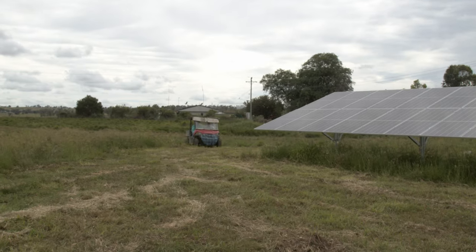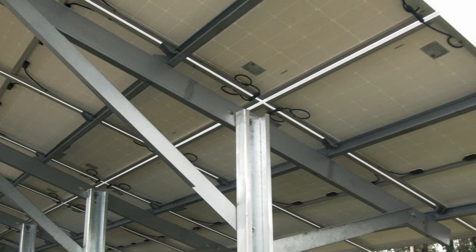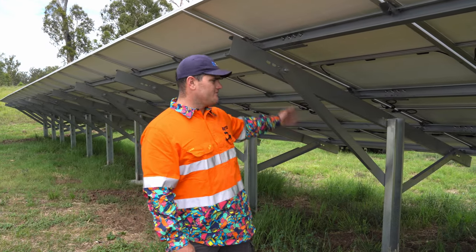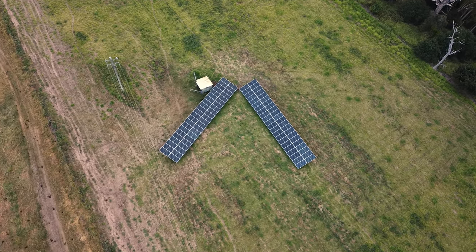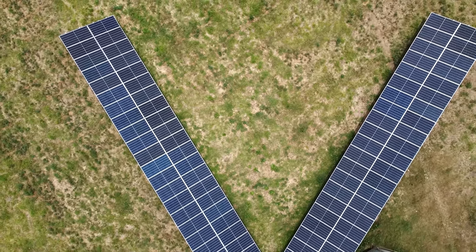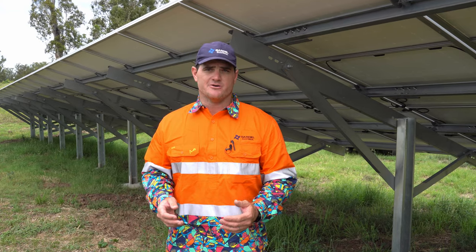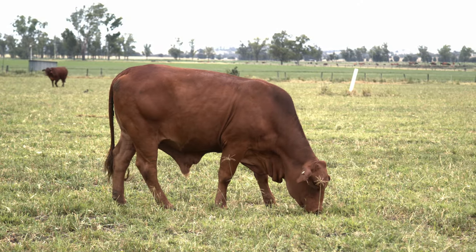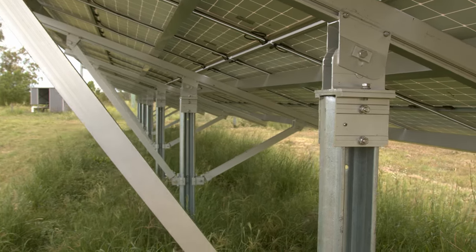On one of the systems we use the Solar Terrace 2, and this is the new UX model of the Solar Terrace PV Easy Rack — it's super simple to put together, only about five bolts and the main structure is up. You can probably tell the panels are arranged in a V. The reason is that we've got 40 kilowatts of panels on a 30 kilowatt inverter. We don't want to face all panels north or the inverter will just sit maxed out for a short period of the day; instead I wanted a more extended morning and afternoon production curve rather than a small peaky one. The panel angle is around 20 degrees, which is optimum for this area and orientation.